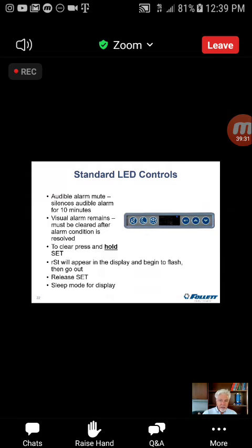The only way to get the same temperature is to take the third-party probe and put it in our bottle, or take our probe and put it in theirs, where you have both probes in the same bottle. Then it should align, all right? So some facilities do that, some facilities don't. So if your facility does not want that as part of their policy, we can just put that display to sleep. It will still display degrees C or degrees F, so you know what it's reading in. And it still gives indicators as to what's happening there.